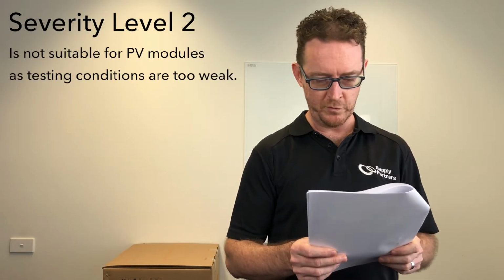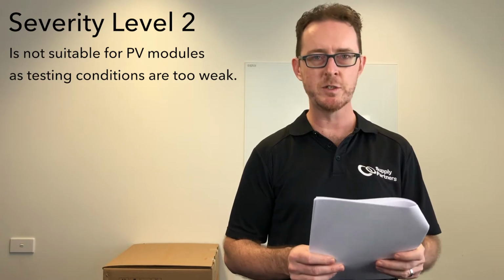And then it goes on to say severity level 2 is not suitable for PV modules as the testing conditions are too weak. So with respect to Australian conditions, apart from some very specific locations in the mountains where there might be snow and then salt used to clear that snow, severity level 1 is the one we want.